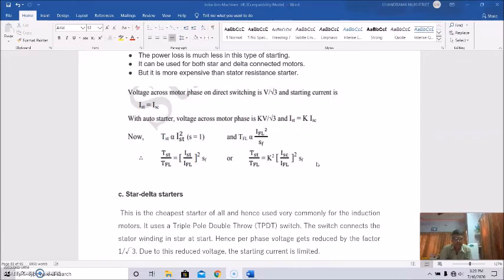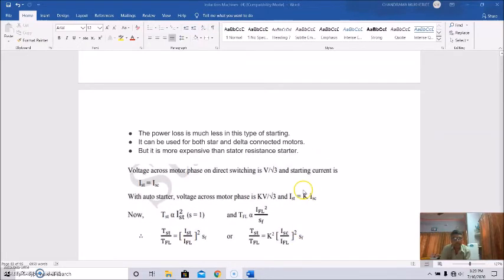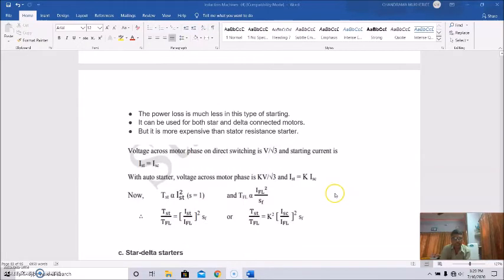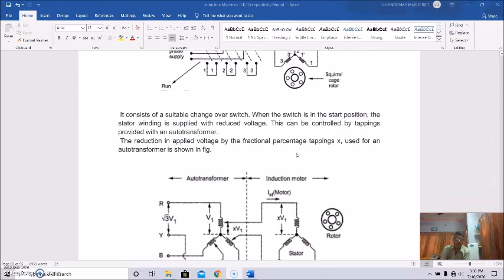And after reaching say 80% of speed, changeover is done from start to run conditions, and the full voltage will be impressed across the motor winding, so the motor gets the full voltage. The main advantage of this type of starter over the primary resistance starter is that the power loss is less, but it is more expensive than the stator resistance starter. And this type of auto transformer starter can be used for both star and delta connected motors. Okay, so that's all about this auto transformer starter.